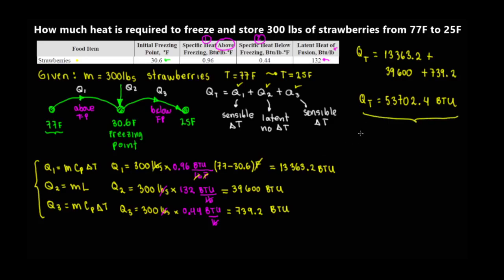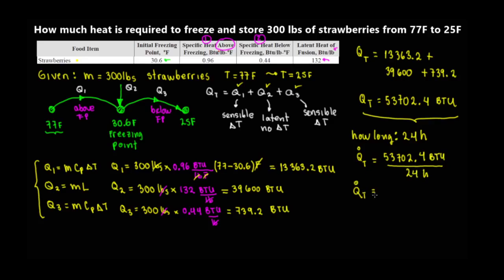Let's extend the problem: how long does this take? Say we want this done in 24 hours. We calculate the heat rate by dividing total heat by time. Heat rate = 53,702.4 BTU ÷ 24 hours = 2,237.6 BTU/hr. That is the required heat removal rate.